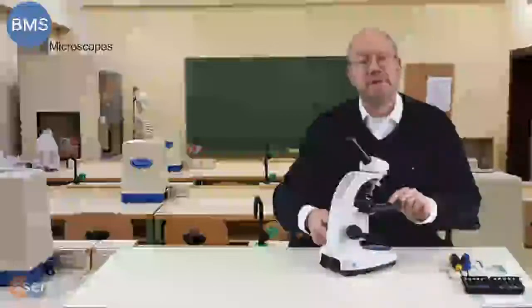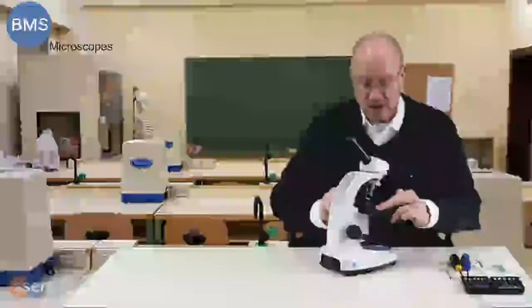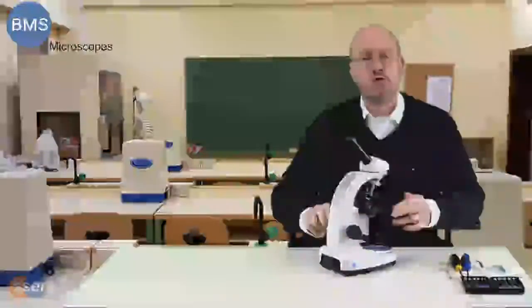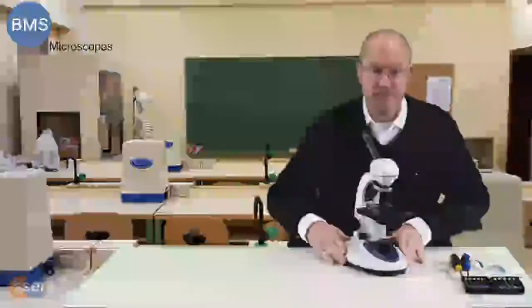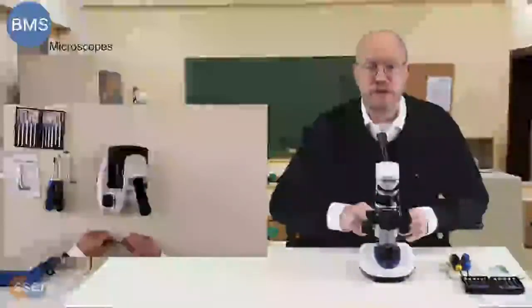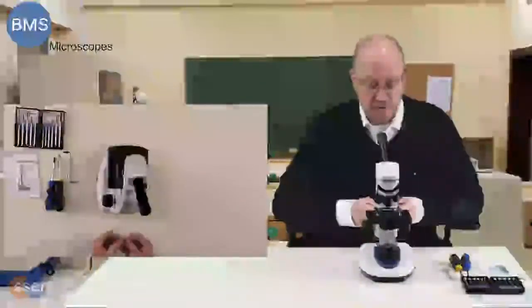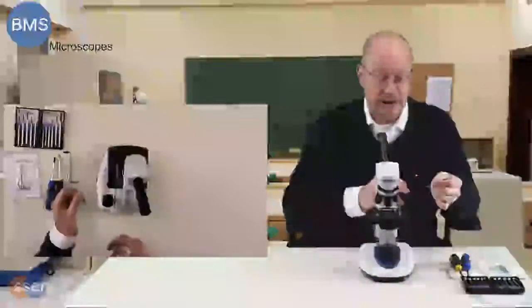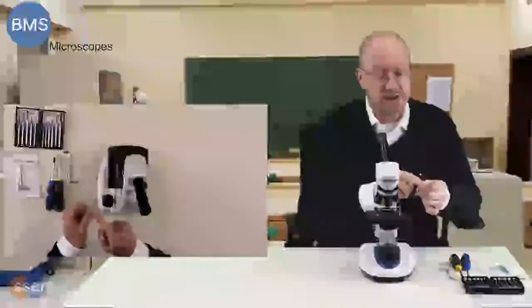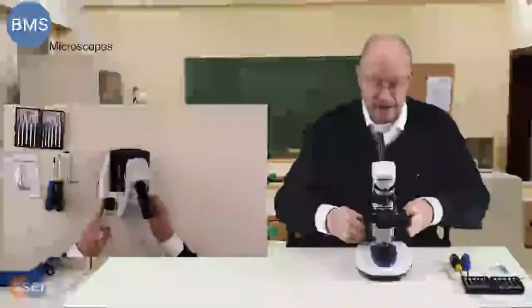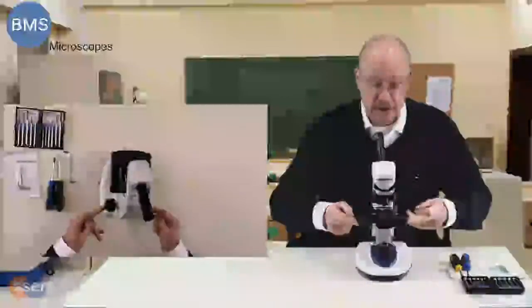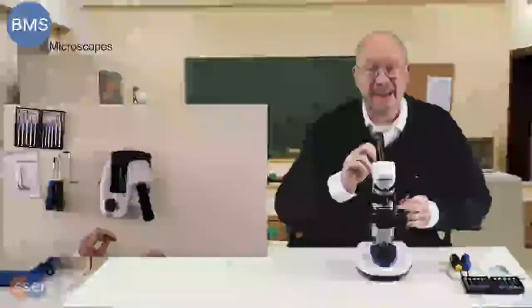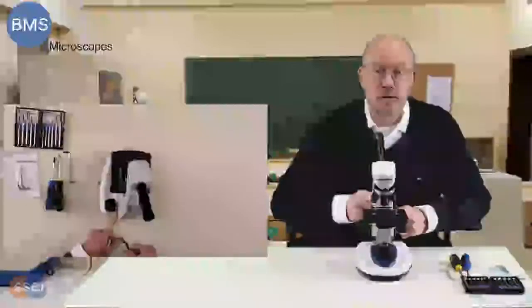What's happening is the following. The stage is being pulled down by gravity, just like this. And that's caused by the fact that the tension on the coarse focusing is not tight enough. So we have to tighten the tension on the coarse focusing. It's done with this little wrench with crescent-shaped ends. And if you look at the axis of the coarse focusing, you will find one part is slightly thicker and you see little holes in there.